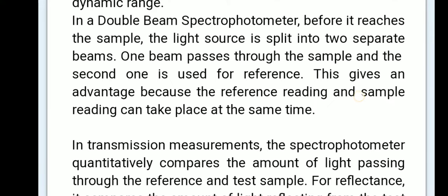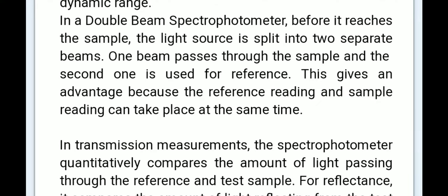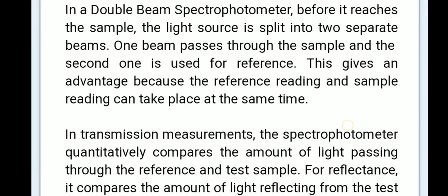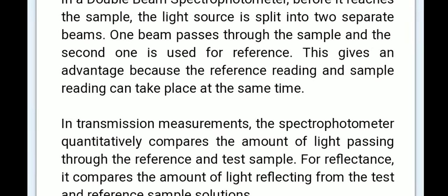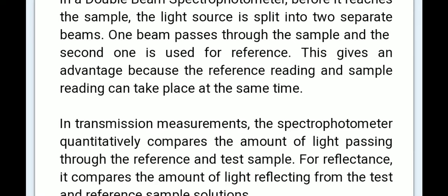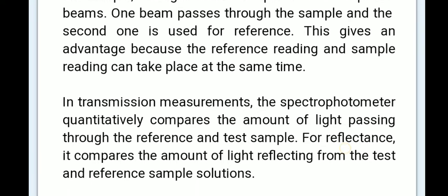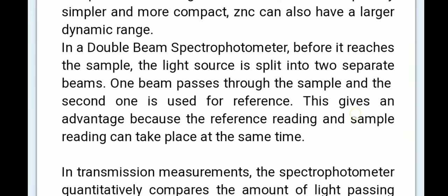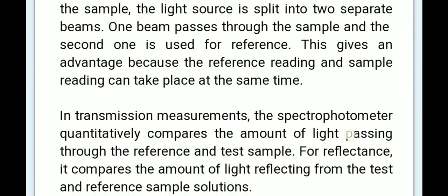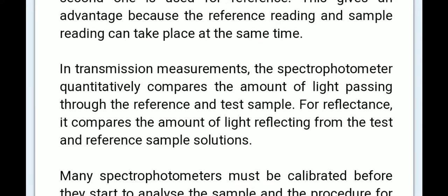In a double beam spectrophotometer, before it reaches the sample, the light source is split into two separate beams. One beam passes through the sample and the second one is used as a reference. This gives an advantage because the reference reading and the sample reading can take place at the same time — the blank and the sample are measured simultaneously. In a single beam spectrophotometer, blank and samples are measured at different times.